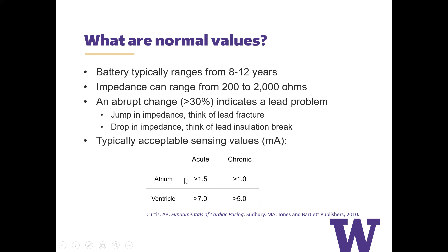And what are typical acceptable sensing values? They are listed in this table. There are lots of things that can be programmed. You can program output threshold, which means how much energy you want delivered over what duration of time in order to capture myocardium. You can also program sensitivity. The reason you want to program sensitivity is that you don't want to oversense or undersense. You don't want to oversense things that are not important, and you don't want to undersense important physiological cardiac signals.